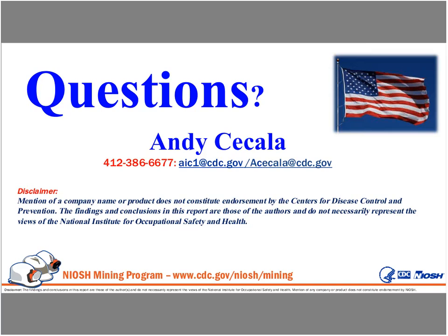Well, what we showed is that the HEPA filter is really so restrictive and loads up so quickly that it's not the best application when you're dealing with dusty environments. So it's hard to say. Ideally, you look at it on a case-by-case basis if you're designing a system. But if you're getting a system from a manufacturer, an OEM, a piece of mobile equipment, their engineers will design a system that will work for you.